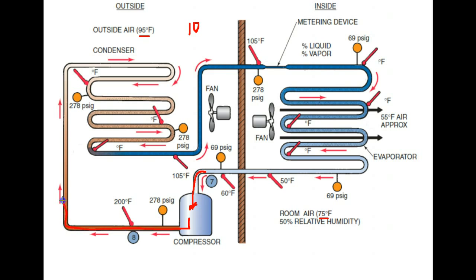The first part of the condensing coil is designed to desuperheat the vapor that has exited the compressor, and it gets rid of that superheat that was added to the refrigerant in the evaporator. It desuperheats and it starts to shed that heat out into the outdoor air because we're at a much higher temperature. Outdoor air is 95, so we're getting rid of this heat rather quickly. And at a certain point designed by the engineers, the refrigerant vapor is completely desuperheated and it reaches its saturation point.